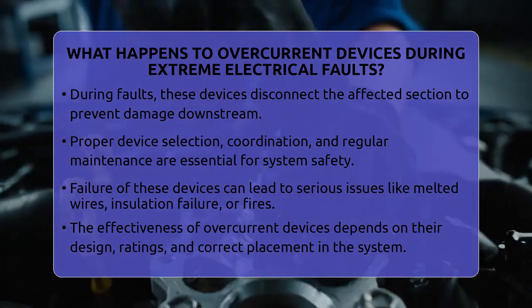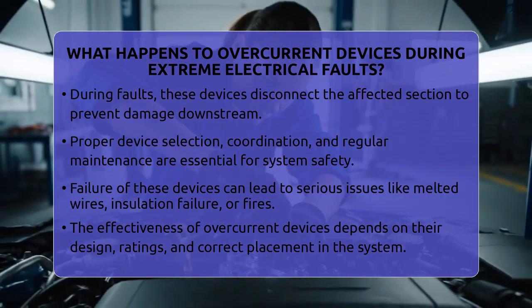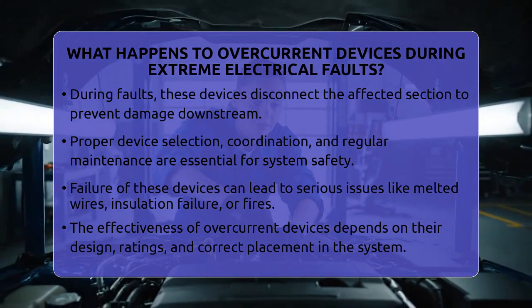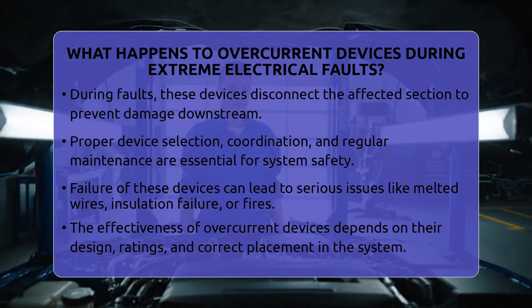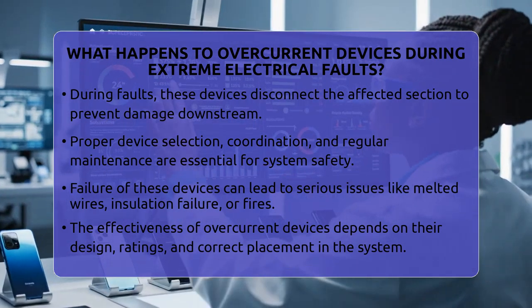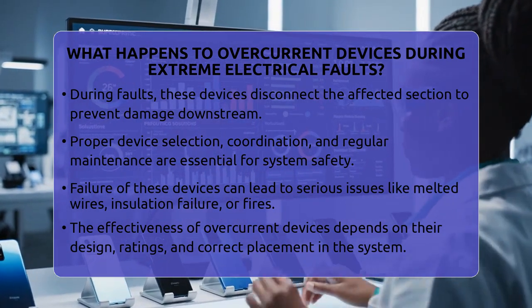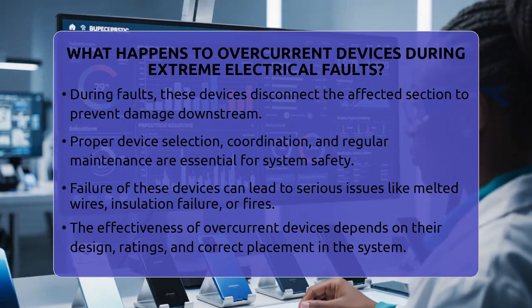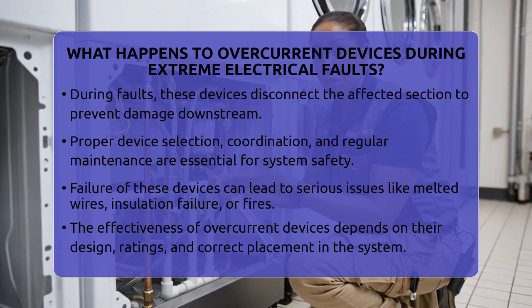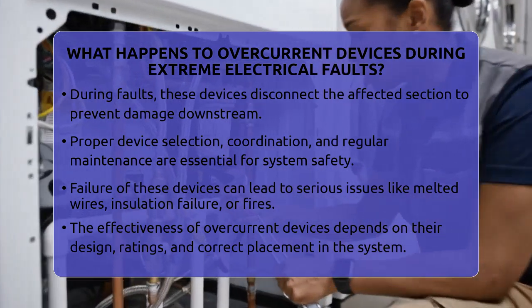In summary, during extreme electrical faults, overcurrent devices respond rapidly. Fuses blow, circuit breakers trip, and relays signal to disconnect the circuit, keeping everyone safe and preventing costly damage. Their ability to act quickly depends on their design, ratings, and correct placement within the power system.